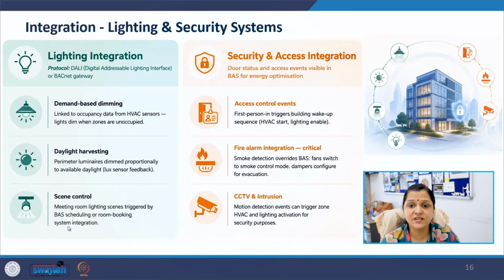Fire alarm integration is especially critical. During smoke conditions, the BAS must switch fans and dampers into smoke control mode so that the smoke is not allowed to enter different areas. This integration supports both safety and operational efficiency.